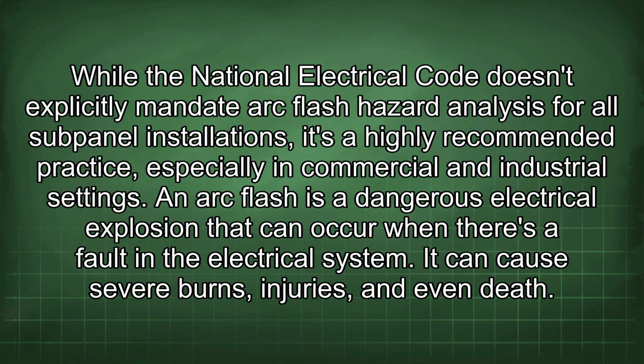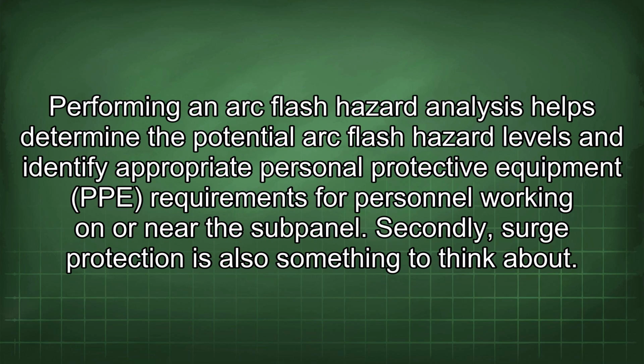While the National Electrical Code doesn't explicitly mandate arc flash hazard analysis for all subpanel installations, it's a highly recommended practice, especially in commercial and industrial settings. An arc flash is a dangerous electrical explosion that can occur when there's a fault in the electrical system. It can cause severe burns, injuries, and even death. Performing an arc flash hazard analysis helps determine the potential arc flash hazard levels and identify appropriate personal protective equipment (PPE) requirements for personnel working on or near the subpanel.